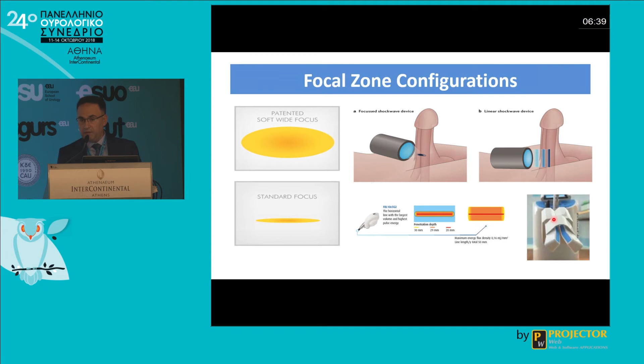But what are the real differences of the devices that are available in the market, at least the Greek market? Let's see. The only electrohydraulic generator today is the ED1000. The others are mainly electromagnetic, and there is one piezoelectric. They all produce focused shock waves, and this is a good thing. The system of Direx, the Renova, has a locked energy flux density at 0.09 millijoules per square millimeter. That's not a big advantage because sometimes, due to energy losses, we need to increase the EFD.